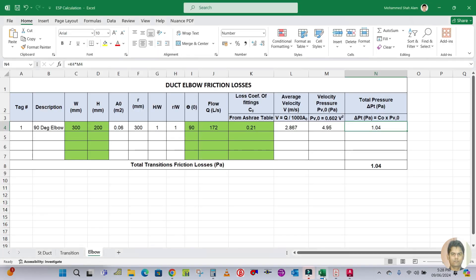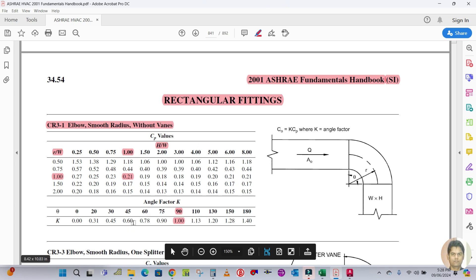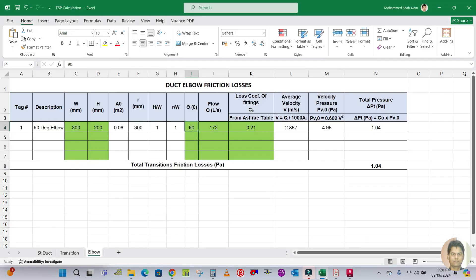If it is a 45-degree elbow, just change the degree to 45 and multiply the k times Cp value by 0.6 to get Co.